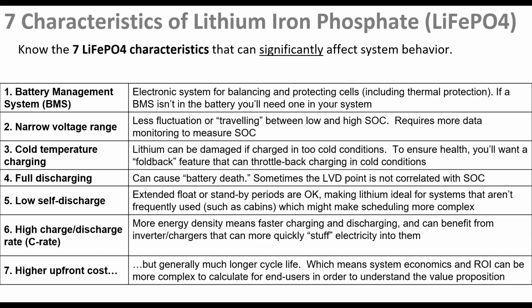The second point is the narrower voltage range, which is a really big benefit because you get less fluctuation. With lead acid, you can see voltages in the 11 volt range as you approach low voltage disconnect, and during cold temperatures as high as maybe the 15s, which is a pretty wide range. But a lot of DC loads really prefer a narrower operating window, and as shown earlier on that graph, you can see how much narrower that is with lithium, which is better for the site overall.